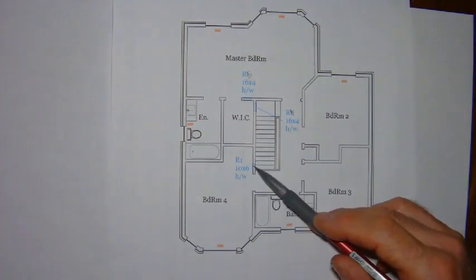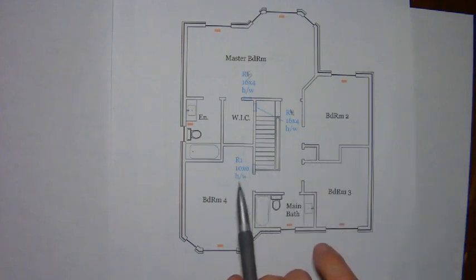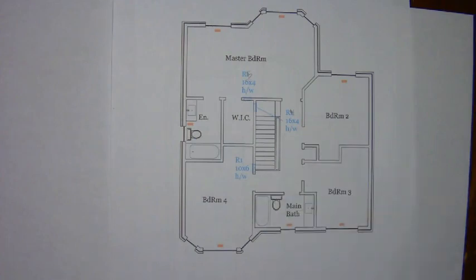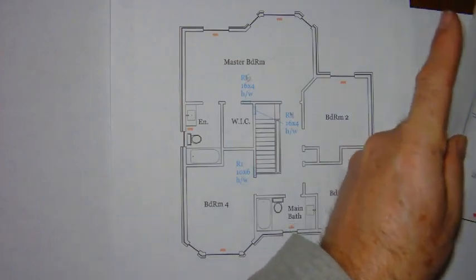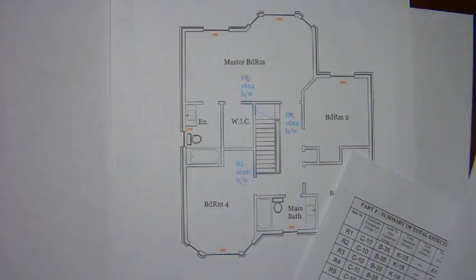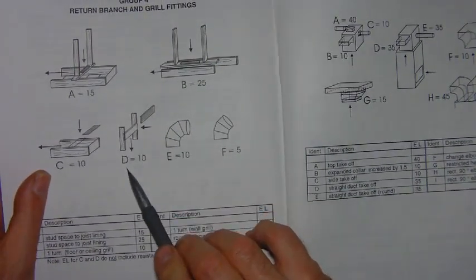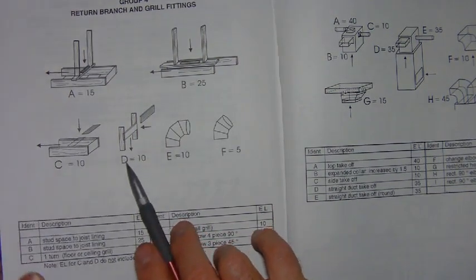So return air number one starts here and so there's a grill. Now the air goes through the grill and turns down into the stud space. That type of grill is a wall grill and it has a resistance of ten equivalent length, and it is a D fitting.